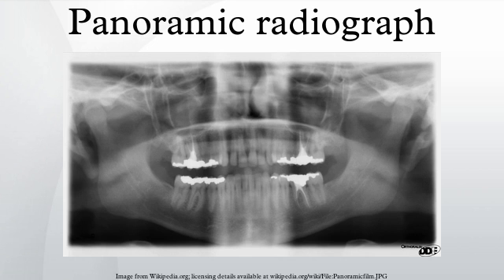The dental panoramic image suffers from important distortions because vertical zoom and horizontal zoom both vary differently along the image. The vertical and horizontal zooms are determined by the relative position of the recorded element versus film and generator. Features closer to the generator receive more vertical zoom. The horizontal zoom is also dependent on the relative position of the element to the focal path; features inside the focal path arch receive more horizontal zoom and are blurred, while features outside receive less horizontal zoom and are also blurred. The result is an image showing sharply the section along the mandible arch, and blurred elsewhere.